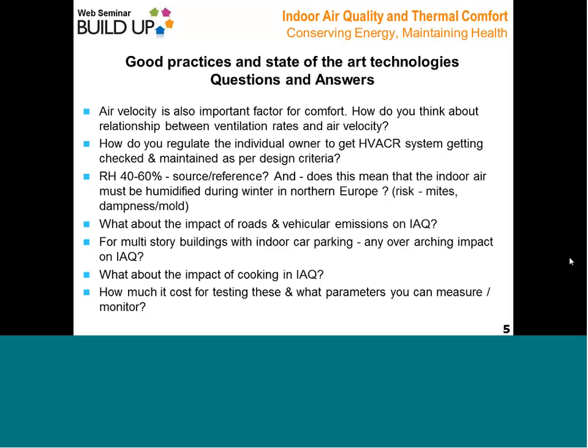There have been a couple of studies from DTU, especially by Fang. They found that normally, if you stay above 20–25% relative humidity, it's not really an issue. Only if you go down really low — like 10–15% — might sensitive people get some symptoms or complaints. But normally it's not necessary to humidify in winter in standard buildings like offices and schools.